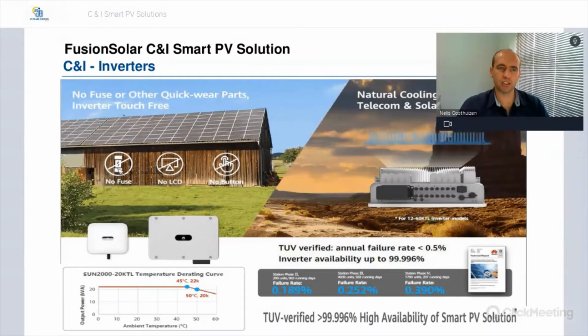So the first thing that's been removed is fuses. Huawei inverters have a fuseless design. It's actually got DC isolation switches at the bottom side of the inverter to disconnect your PV input strings. There's no LCD screen, and there's also no buttons. A button is something that people tend to like to press and cause havoc in the system. So the whole approach on the Huawei system was to have it more reliable, and in the modern age that we live in, everything is accessible either via your cell phone or the internet on your laptop.